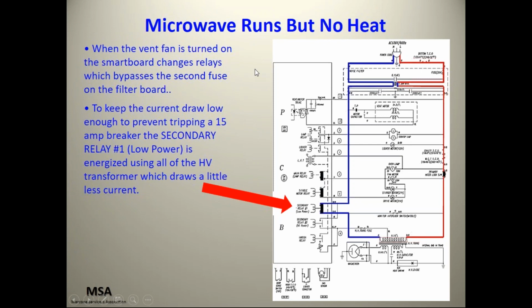When the vent fan is turned on, the smart board changes relays, which bypasses the second fuse on the filter board to keep the current draw low enough to prevent tripping a 15 amp breaker. The secondary relay, which is low power, is energized when using all the high voltage transformer, which draws a little less current. So when the customer is running the vent fan, to make sure that the microwave itself doesn't draw more than 15 amps, it doesn't use that secondary relay, which incorporates that fuse. It's using the primary relay, which energizes the entire filament. So it's a good way to check if the fuse is blown. Turn on the vent and see if it works.